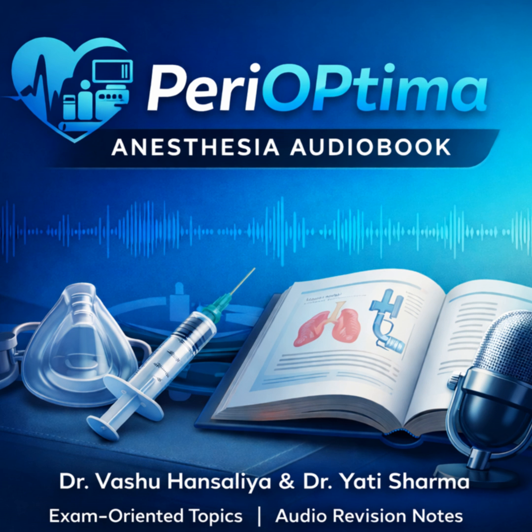That is a vital distinction. So fail-safe guards the supply, hypoxic guard guards the knobs. Perfectly put. And remember, neither of them protects you against a pipeline crossover. Yeah. If the maintenance team accidentally hooks up the nitrogen tank to the oxygen pipe in the wall, the machine sees pressure, so the fail-safe is happy, and the knobs are turning in ratio, so the hypoxic guard is happy. But you are killing the patient.